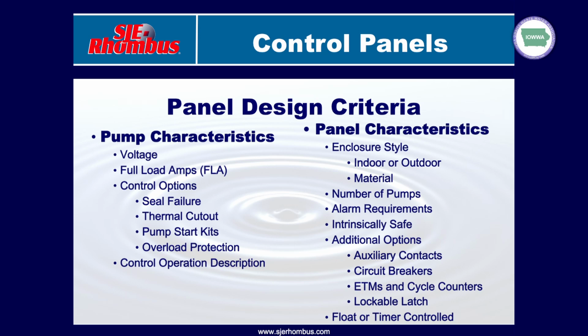Some of the things we need to know to size a panel properly and get you what you guys need or get the homeowner what they need. Some of the questions we have, we need to know characteristics of the pump. We need to know the voltage of the pump, whether it's 120 volt or 230 volt. We need to know the full load amps of the pump so we can size the circuitry inside the panel appropriately to handle what kind of load the pumps are going to require.